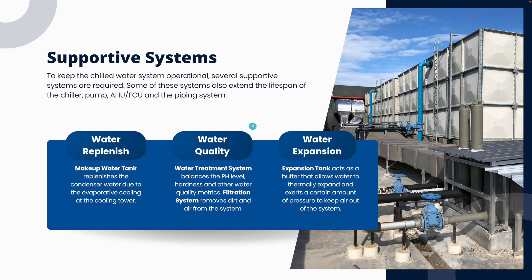The second supportive element is water quality. Within a piping system we need to maintain a certain pH level and hardness, and keep chloride levels in check, so the system performs at its best. This is handled by the water treatment system, using either chemical or non-chemical treatment. For chilled water — which is in a closed loop — we only need to balance the pH once. However, for condenser water, which is exposed to outside weather at the cooling tower, it can bring in sand, dirt, bacteria and viruses, so water treatment is mainly required on the condenser water side.